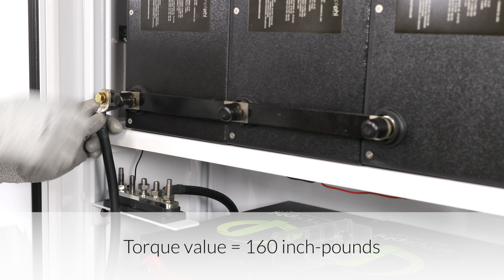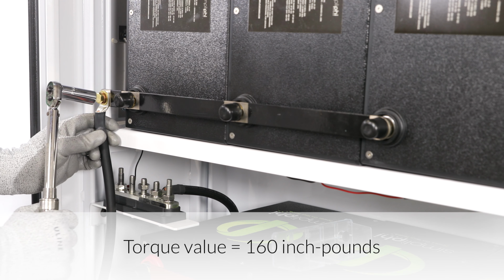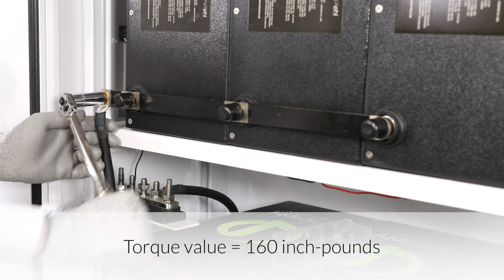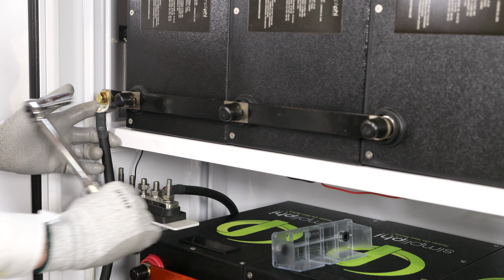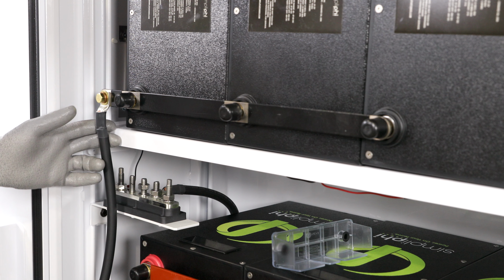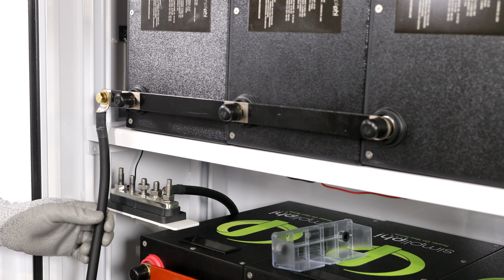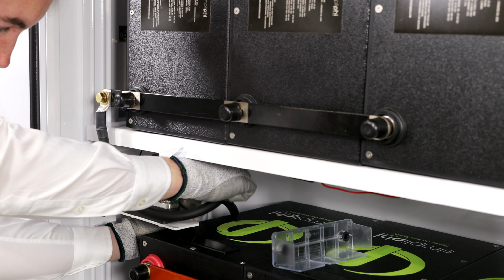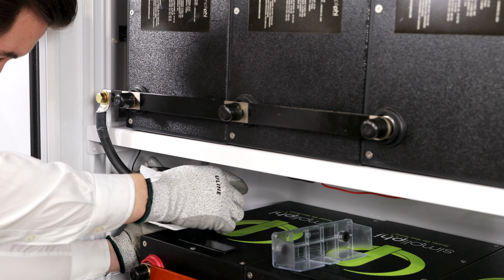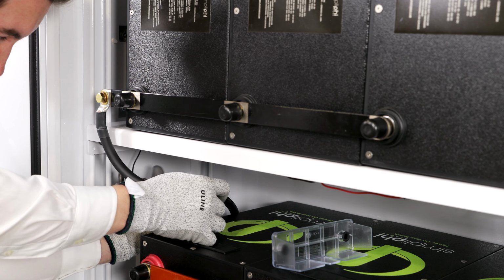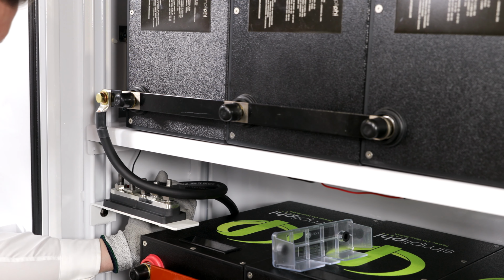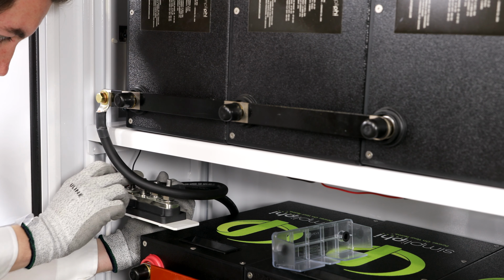Secure the cable lug to the bus bar by tightening the brass hex head cap screw to 160 inch-pounds of torque. While tightening, secure the lug with the other hand so that it doesn't twist or move. Route the cable down, back, and around so that it circles back to the 5-point terminal block. This cable will not be routed through the gap between the shelf and sidewall.